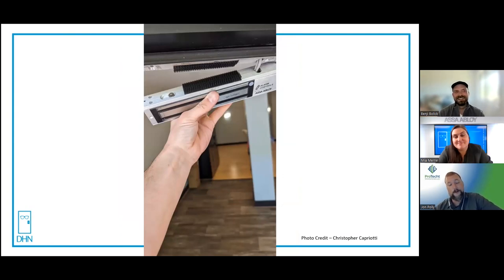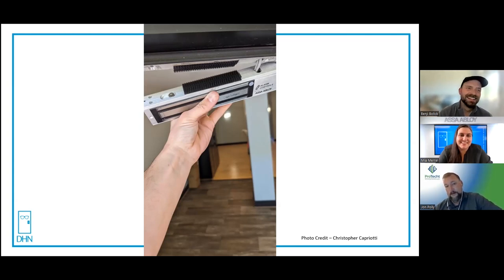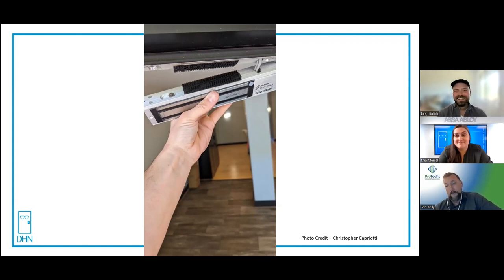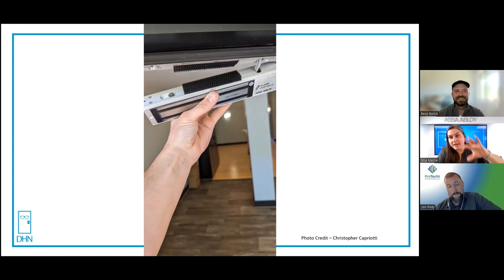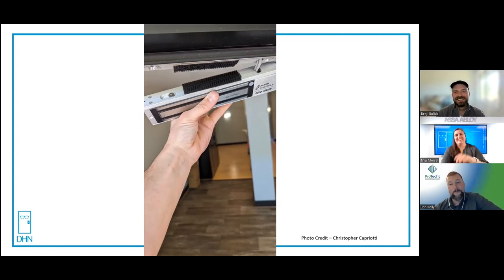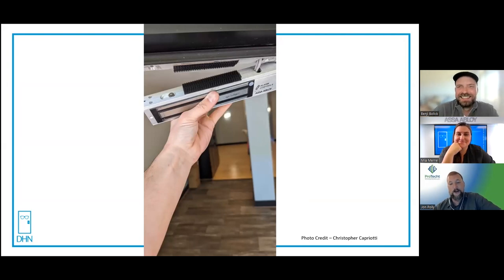Okay, kudos if you're going to put it up with velcro, at least you use the really good velcro. But that's a 300-400 pound maglock. You're going to pull open that door and the maglock is going to come with you. Don't worry, it doesn't look like there's a lot of extra wire, so it's not going to go far.